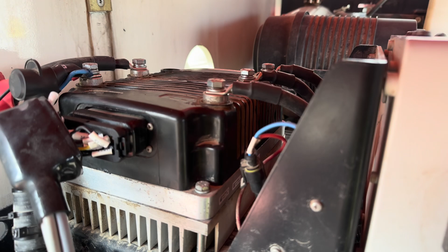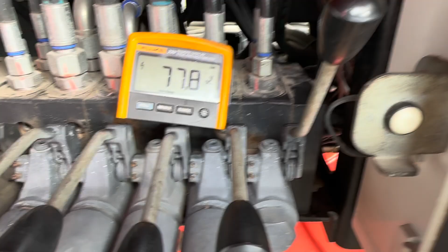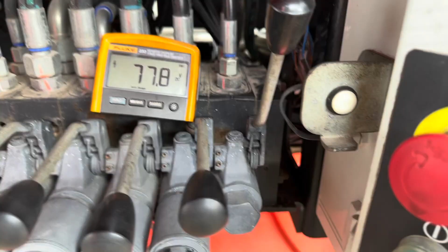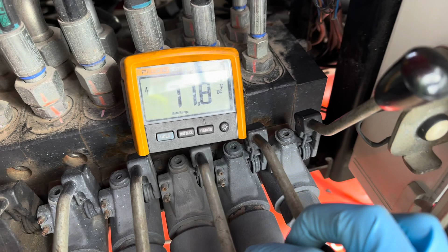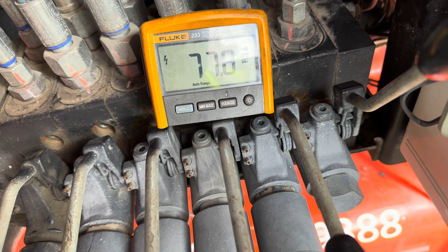So let me do some checks. I will do the checks between the phase wires and the case, just for the short circuit, and then go from there. So just before I try the new controller on it, I will try to see what sort of voltage I have on the startup. So now 77 volts on a U-phase wire. I switch the machine on, and it's gonna go to start.